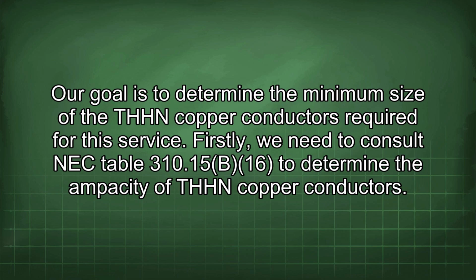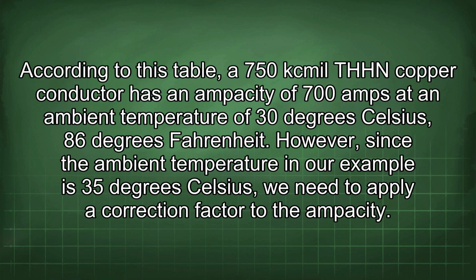Firstly, we need to consult NEC Table 310.15(B)(16) to determine the ampacity of THHN copper conductors. According to this table, a 750 kcmil THHN copper conductor has an ampacity of 700 amps at an ambient temperature of 30 degrees Celsius, 86 degrees Fahrenheit. However, since the ambient temperature in our example is 35 degrees Celsius, we need to apply a correction factor to the ampacity.